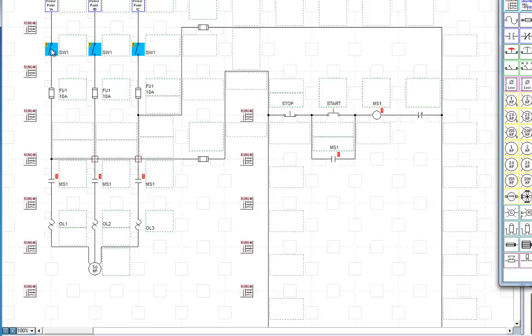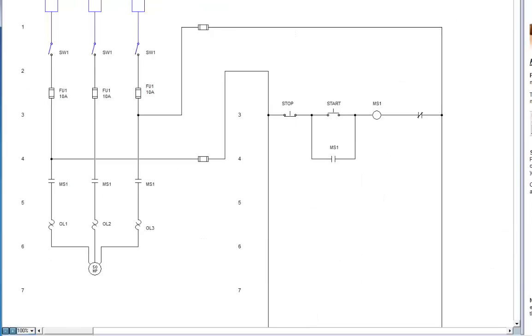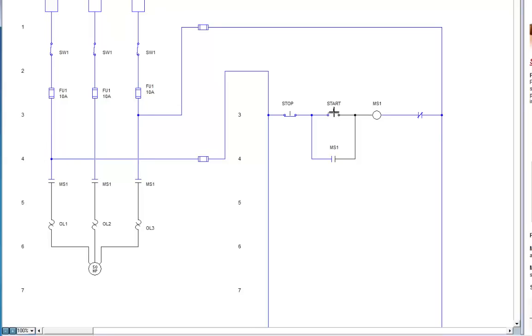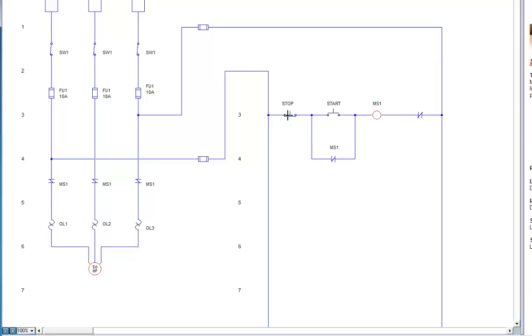So let's go up here and look at the simulation. I can close this. They all close. Now you see we have power everywhere here. Now push the start button. Energize the coil. These contacts close. These contacts close. And our motor is running. Hit the stop button. Everything stops. Hit the start. And we trip the overload.